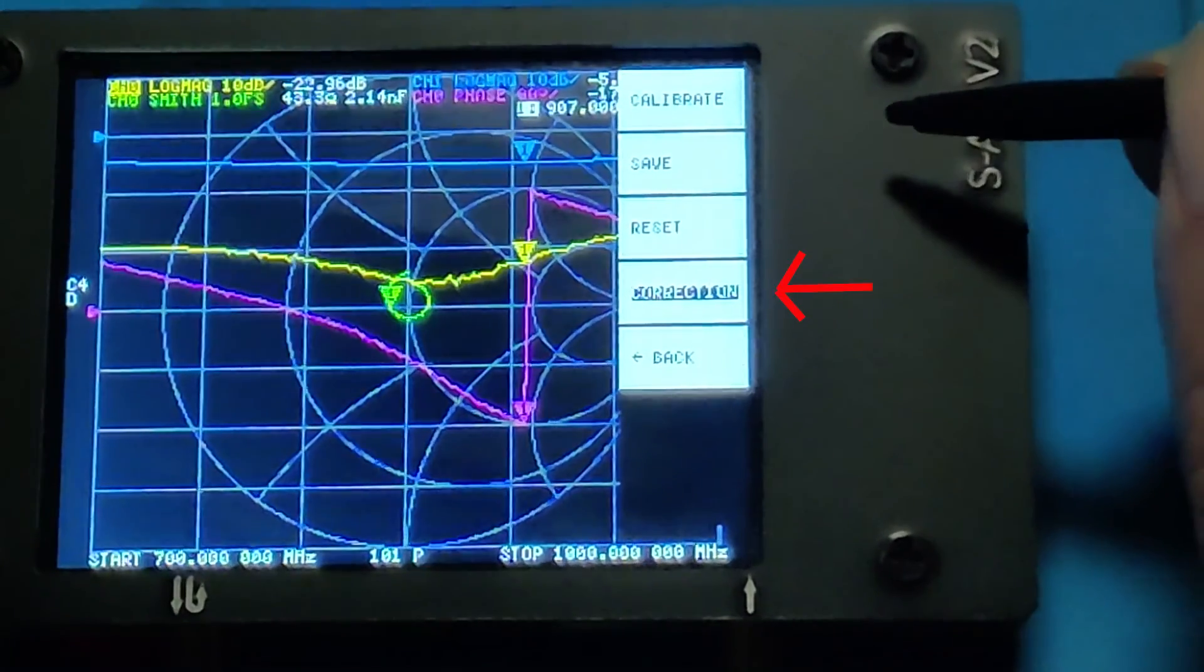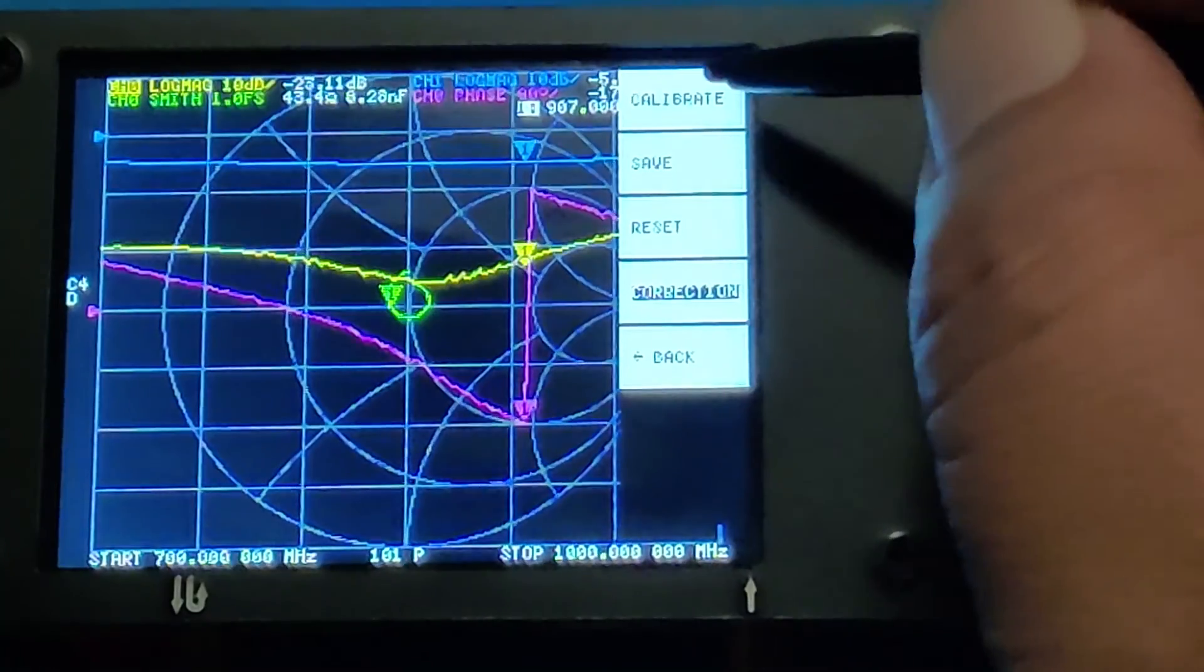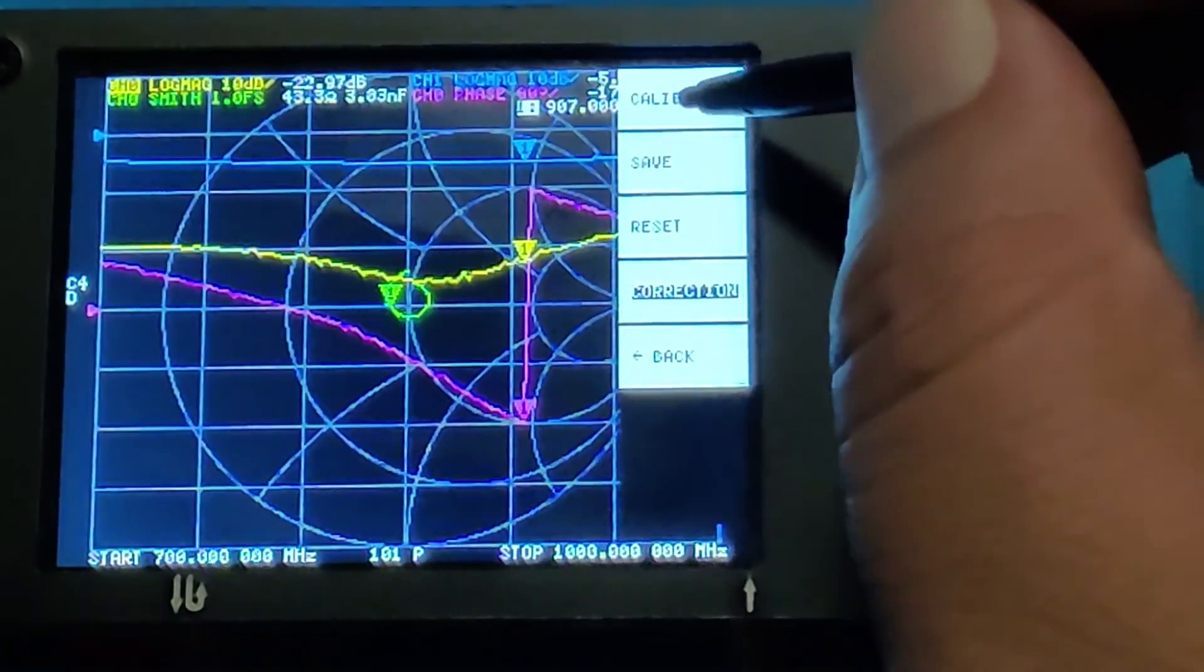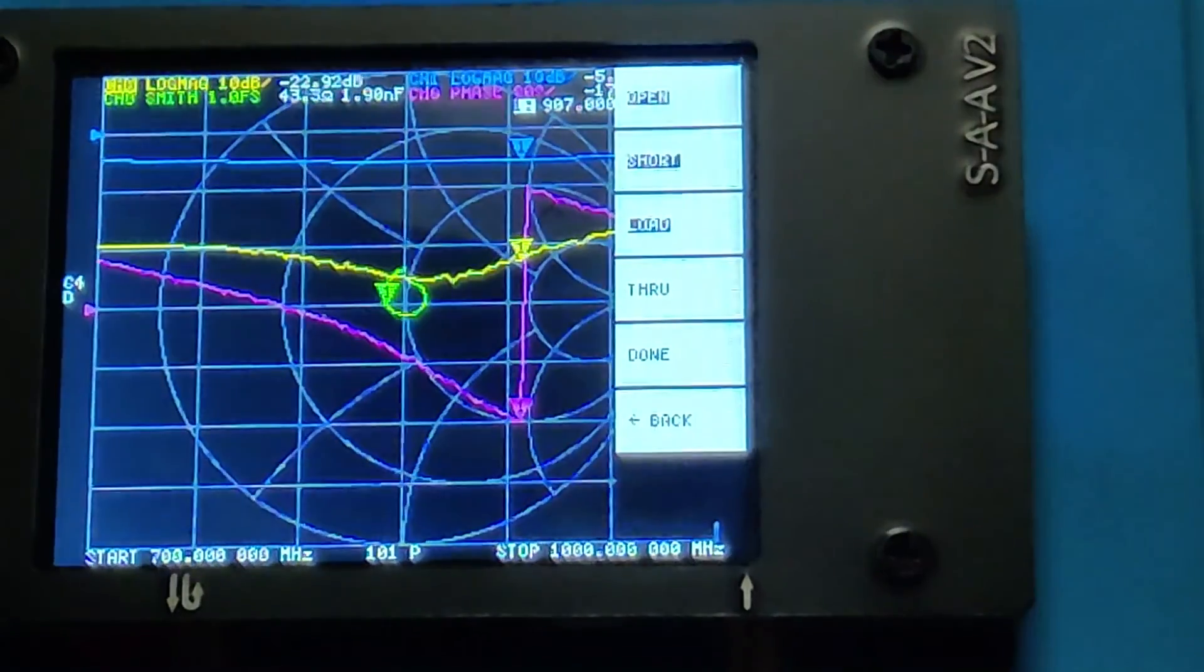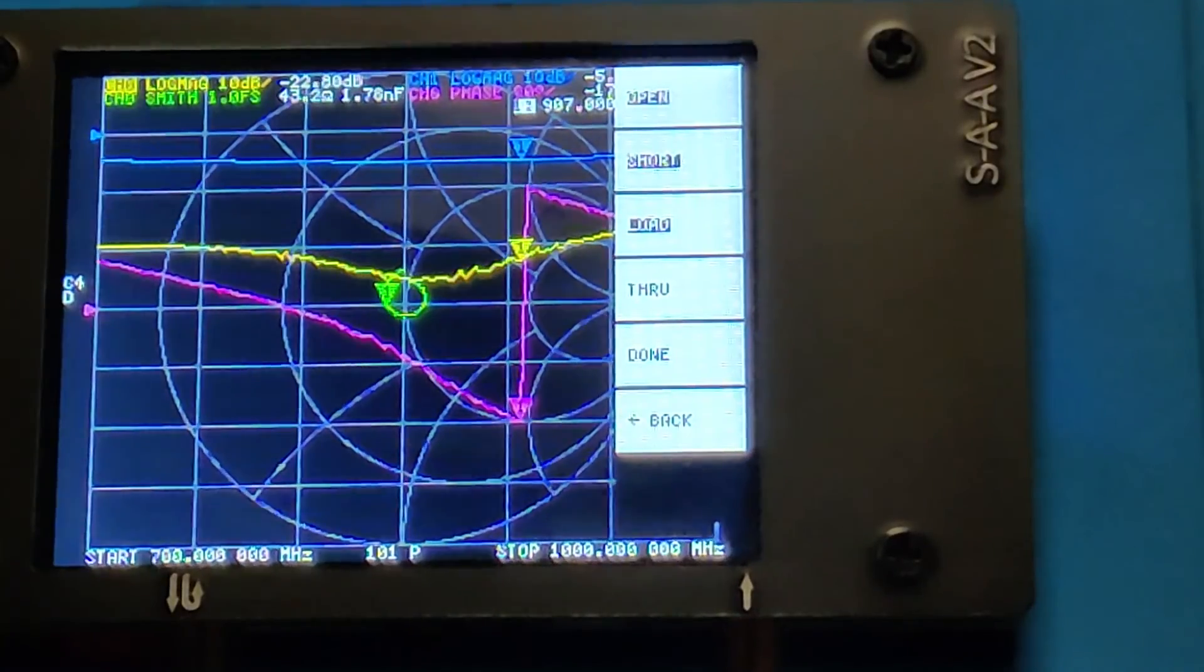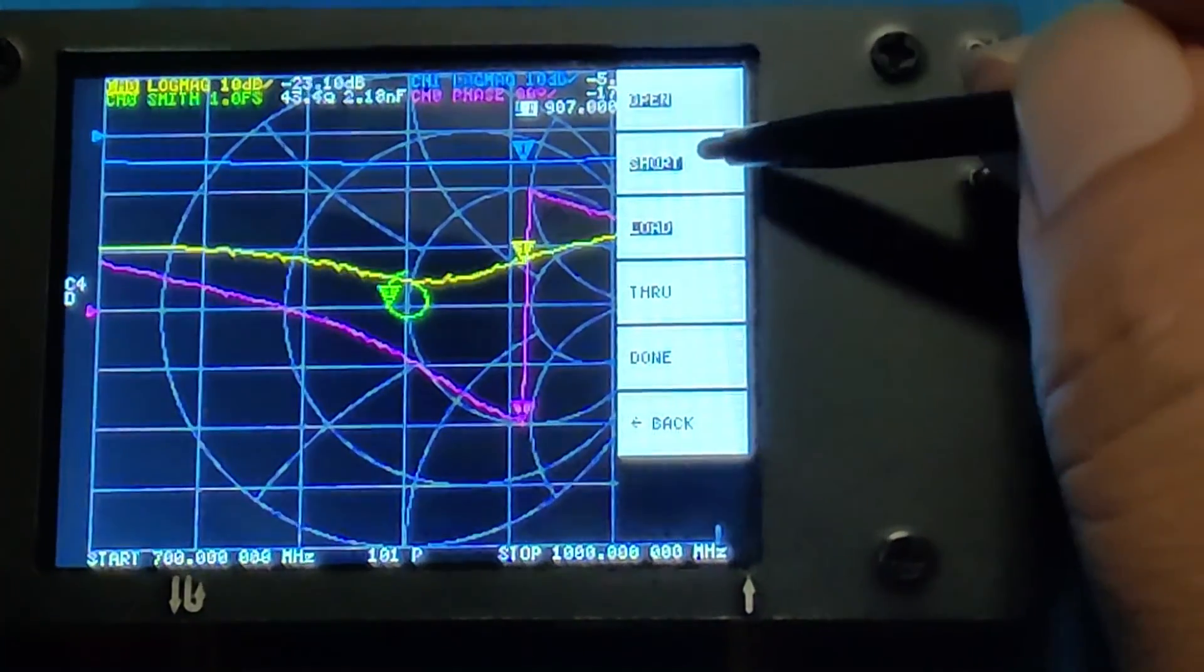Just keep the correction highlighted and click on calibrate. Now you can see we have open, short, and load highlighted. That means they are already calibrated.